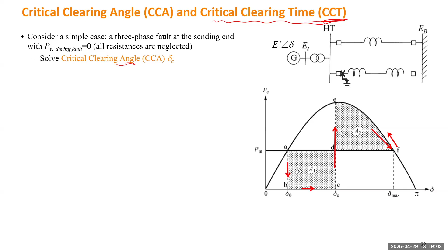For each generator, we can study the local critical clearing time, like this generator against the rest of the system, using something like a single machine infinite bus system model. And we can use this critical clearing time as a threshold for local protection. So the protection time needs to be shorter than this critical clearing time to make sure the generator is stable under disturbance. So here we assume a simple case.